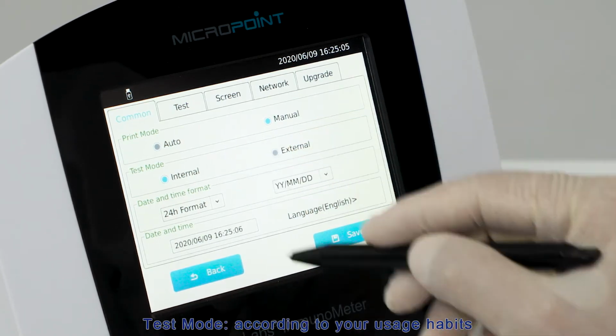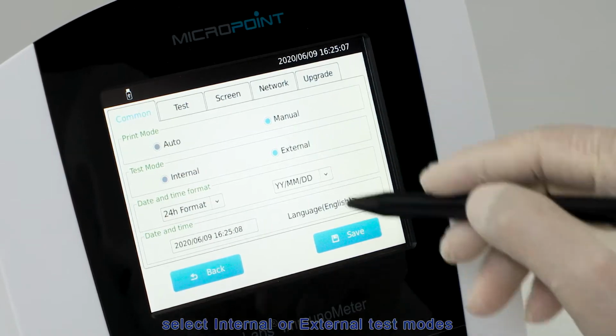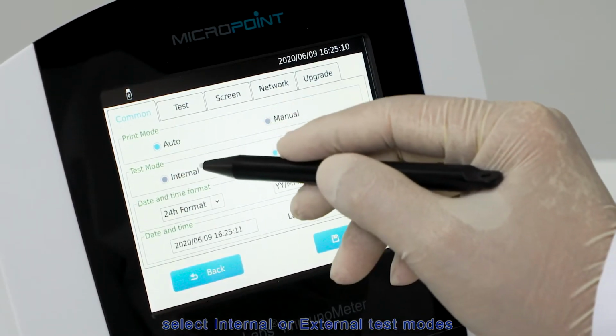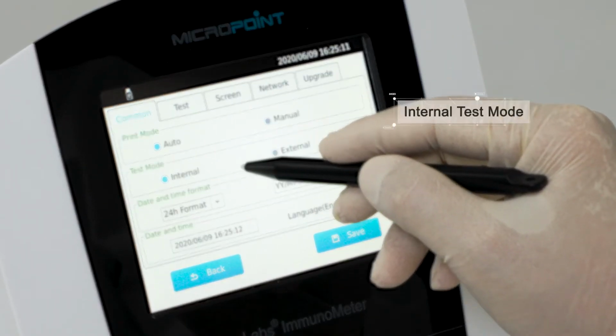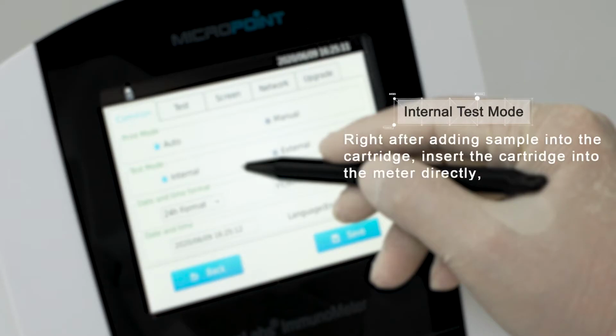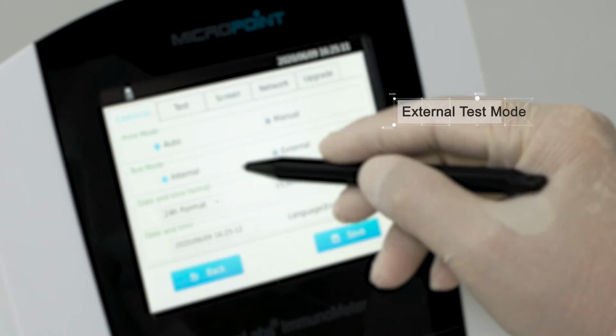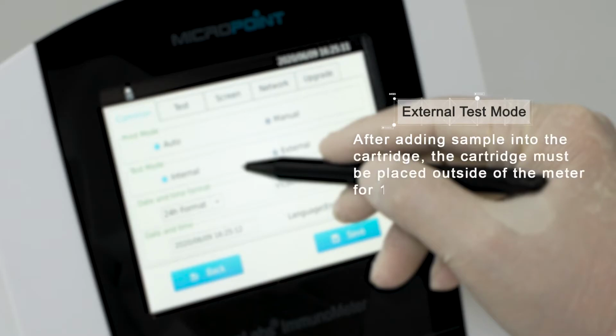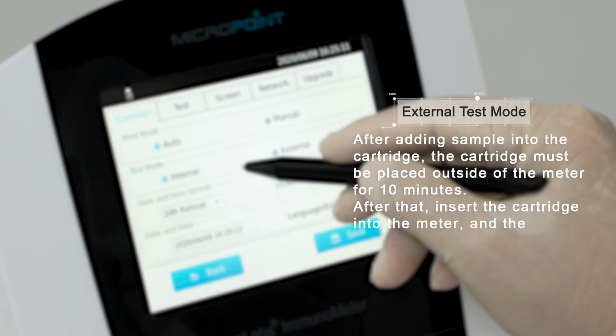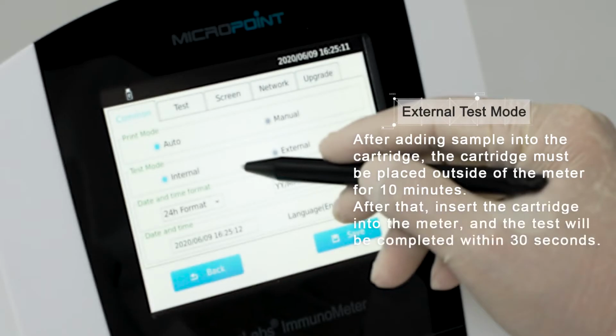Test mode. According to your usage habits, select internal or external test mode. Internal test mode means right after adding sample into the cartridge, insert the cartridge into the meter directly, and the test is completed automatically within several minutes. External test mode means after adding sample into the cartridge, it must be placed outside of the meter for 10 minutes. After that, insert the cartridge into the meter and the test will be completed within 30 seconds.